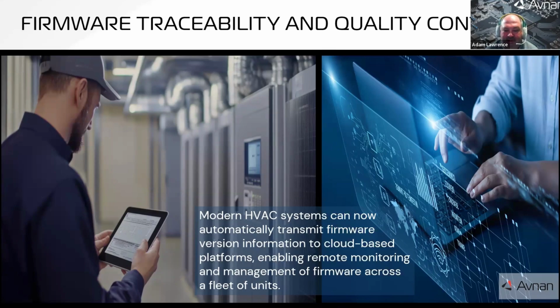The real value of traceability shows up when there is an unusual intermittent fault in the field. Suppose we start getting reports that a certain model heat pump is sporadically throwing a false pressure alarm. If we know these units are running firmware version 3.1 and our logs show we updated the pressure sensor algorithm in version 3.2, that's a huge clue. We can quickly zero in. Maybe version 3.1 had a bug that was fixed, so the solution is simply to update those units to current firmware. From the manufacturer's perspective, this is about protecting quality and reacting fast to issues. It can be the difference between a minor field bulletin or a full-blown recall.